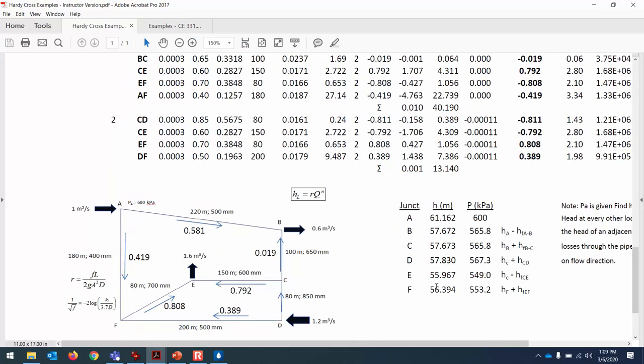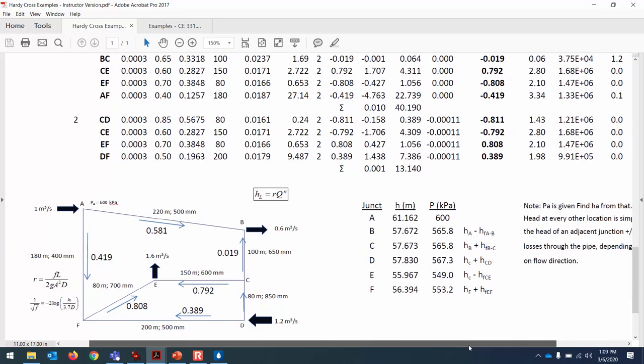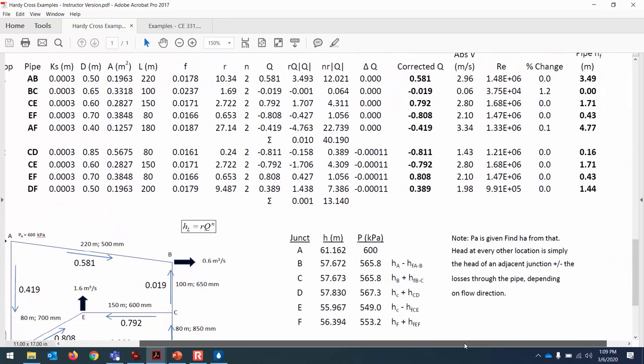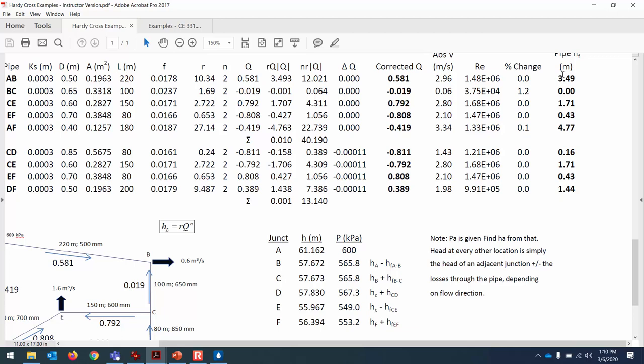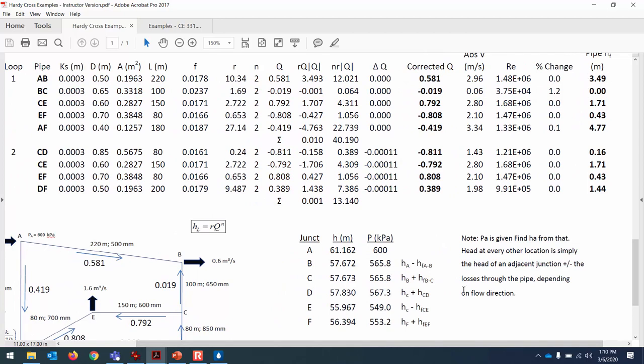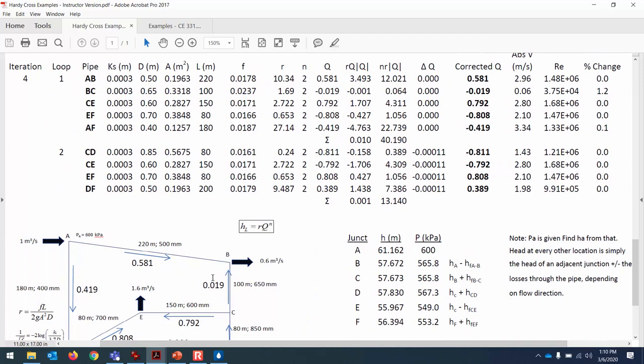At the bottom of the page, the flow direction, flow rate, and pressure at each location are shown. The flow rate through pipe AB was 581 liters per second (0.581 cubic meters per second). The head loss through that pipe was calculated using the Darcy-Weisbach equation: the R value times the flow rate squared, giving a loss of 3.49 meters of head. Assuming all junctions are at the same elevation, the pressure at B equals the pressure at A minus the head loss through AB.